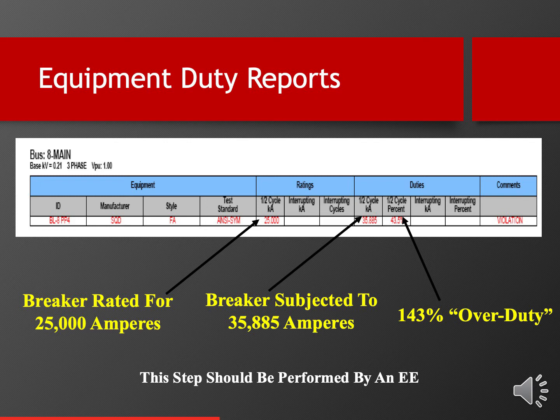So for example, here we see a system where the rating of the device is 25,000 amperes of current flow. It's actually subjected to 35,885 amperes, which is 43% over duty, or over its rating. So from a worker's standpoint, this equipment duty report, I would have this on my person pretty much all the time when you're troubleshooting, because the deal is you never ever reset a circuit breaker on something that's 90% of its duty rating or more. So this is something, as I said, when I did the work, we often would reset devices into situations which could be catastrophic, and as a result of that, this information is very useful, and this step here also should be performed by an EE. Let's go to the next slide.